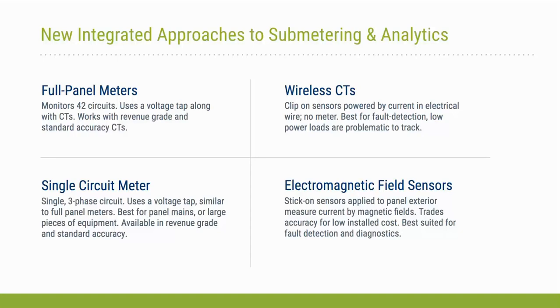The first one would be full panel meters, which monitor up to around 42 breakers in a single panel. They tend to use voltage tap as well as current transformers, and they either work with revenue grade or standard current transformers. Then we have another category, which we describe as wireless CTs. These are clip-on sensors, so they're a lot easier to install. However, they don't require an electrician for the task, and they don't need a meter in this case. So they only use a CT and extrapolate power consumption out of an estimate of voltage, rather than actually calculating voltage as full panel meters do.